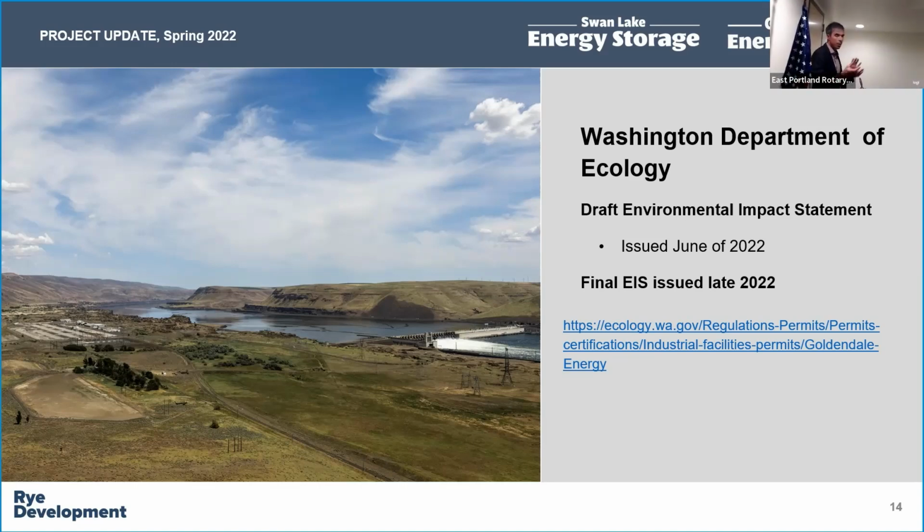Yeah, so the pump turbines for the projects can accommodate a project of real small scale. You could build a pump storage project with just the right size pump turbine and the right size penstock in one of our water storage towers here in Portland, of small scale. But would that be competitive with the lithium ion battery in your garage? Probably not. There would be more parts and a cost to it that wouldn't make it as comparable. Could you do it? Certainly, all the technology's there. And then you size up from there. You're going to have different size turbines, different size penstocks, or the tunnels that connect the two reservoirs, and different size powerhouses, depending on the size of the project.